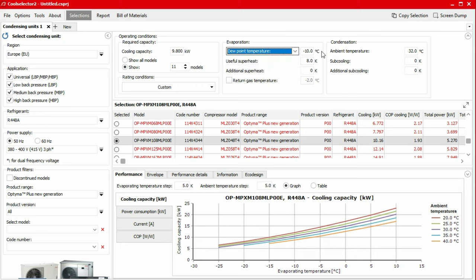Specifying useful superheat in the evaporator and additional superheat between the evaporator outlet and compressor inlet is important for the correct selection and calculation of compressor and condensing units, especially if we have long suction lines in the system. A higher useful superheat would reduce the mass flow rate in the evaporator slightly.